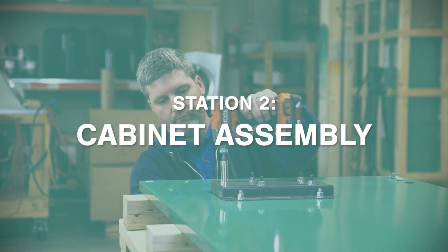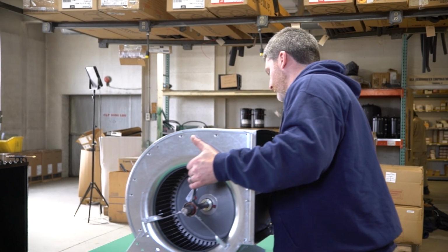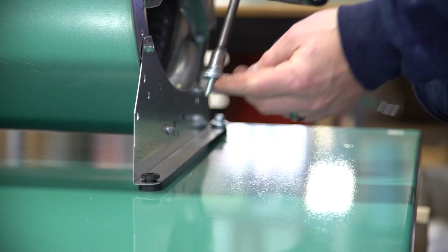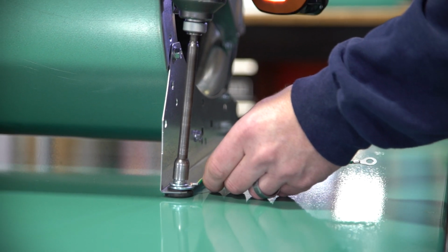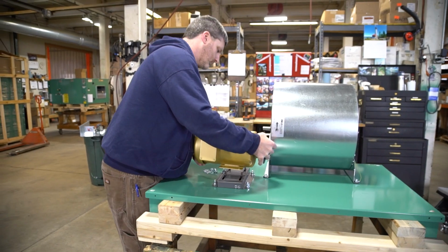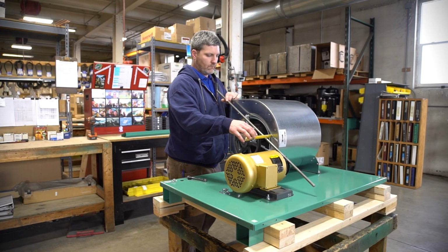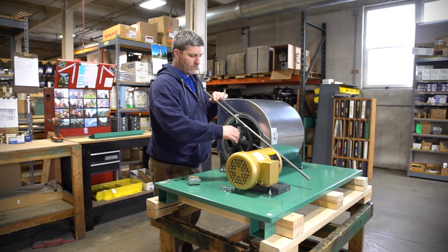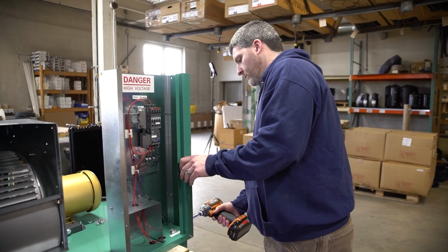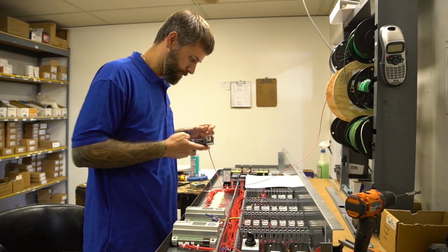I start with verifying the parts that are pulled to make sure we're installing the right parts. Then I continue with taping off whatever needs to be taped off, and I start installing the motor base and blower, then align the pulleys on each. I mount the electrical box and continue to wire the motor and whatever other components get installed. Sometimes there's more temperature sensors or whatever they throw in there. Then I continue to install the cabinet parts, the tops, and the doors.